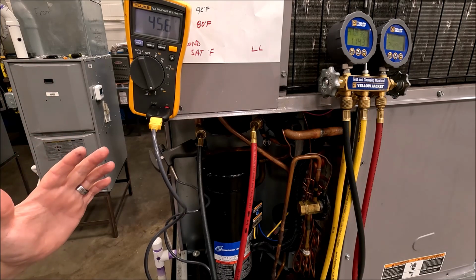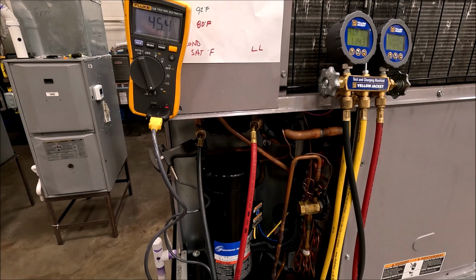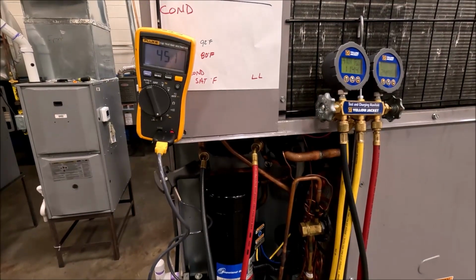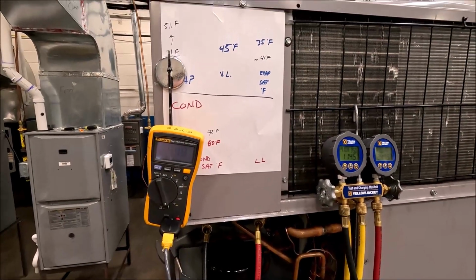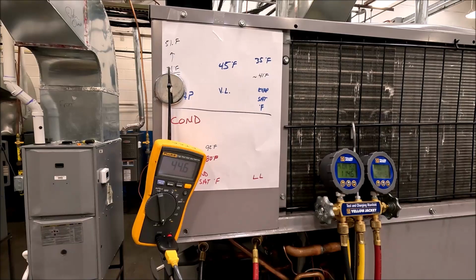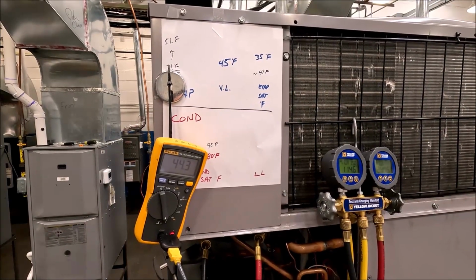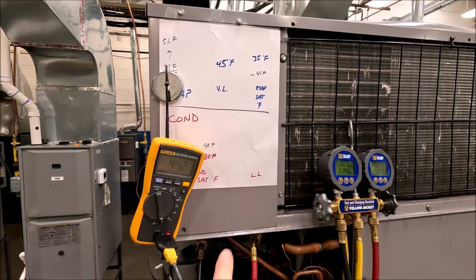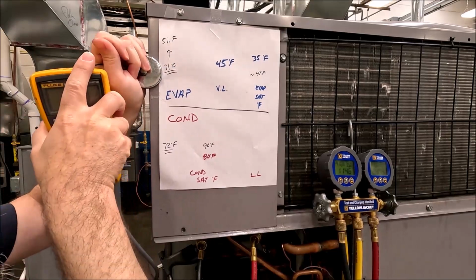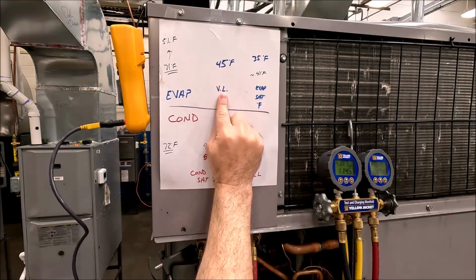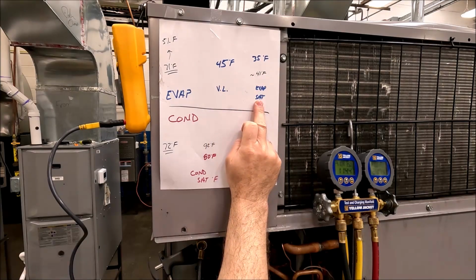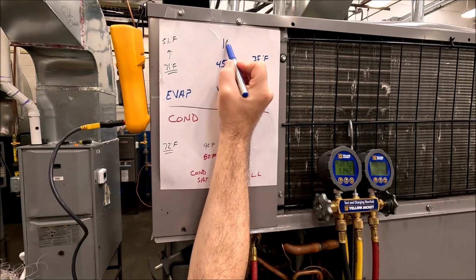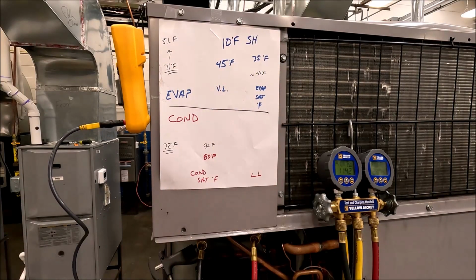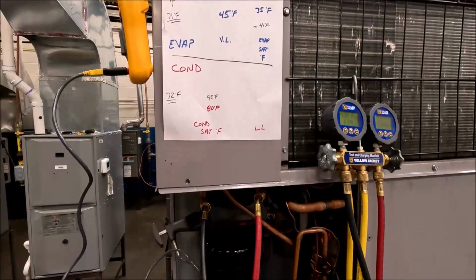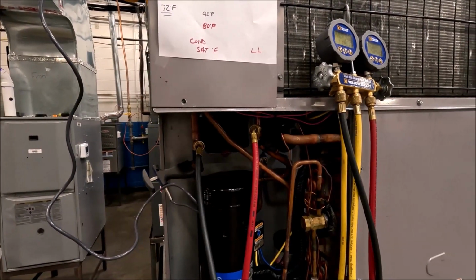So I know I've got superheat. I can do the formula now and figure out just how much. As we're doing this, you can see I've got a 45 degree vapor line and a 35 degree saturation temperature. What that's going to give me is 10 degrees of superheat. Okay. We could flip around and do another check for our subcooling.